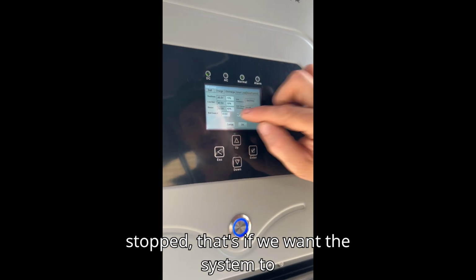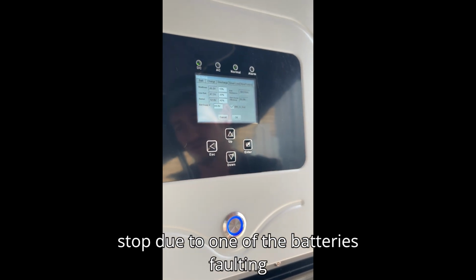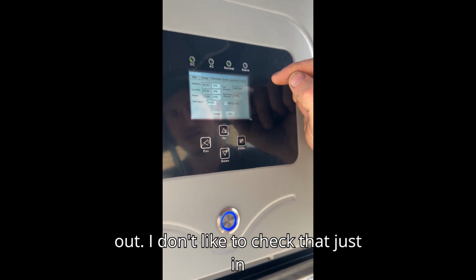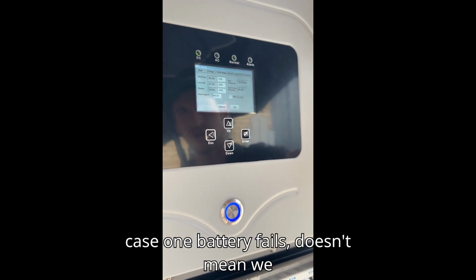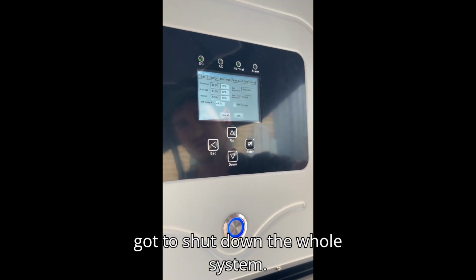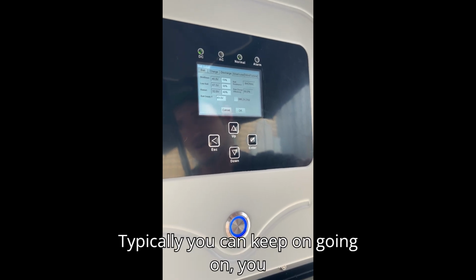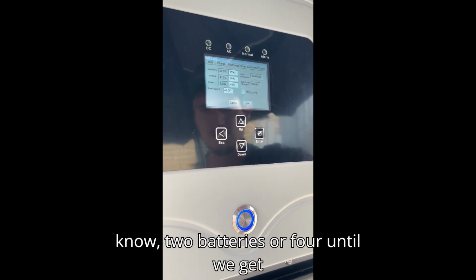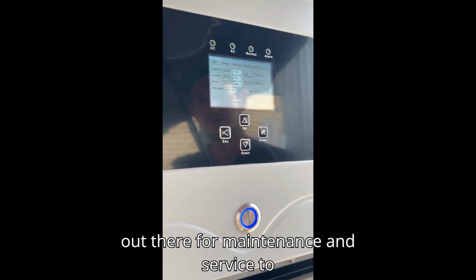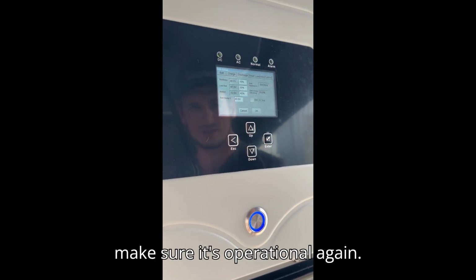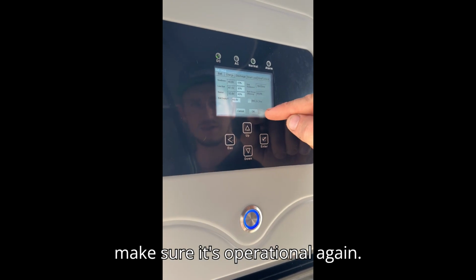BMS error stop, that's if we want the system to stop due to one of the batteries faulting out. I don't like to check that, just in case one battery fails. Doesn't mean we have to shut down the whole system. Typically you can keep on going on 2 batteries or 4 until we get out there for maintenance and service to make sure it's operational again.